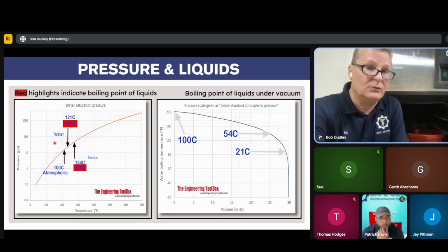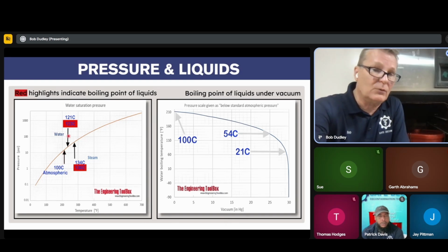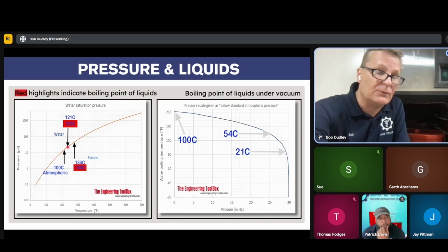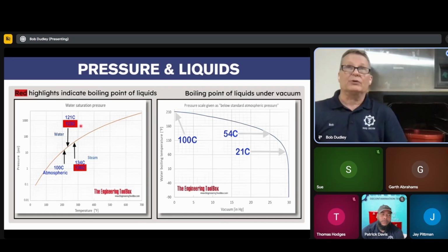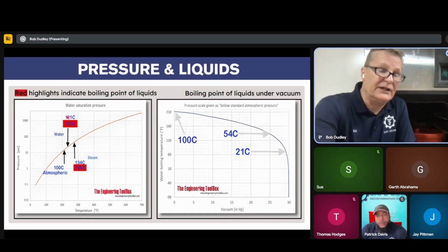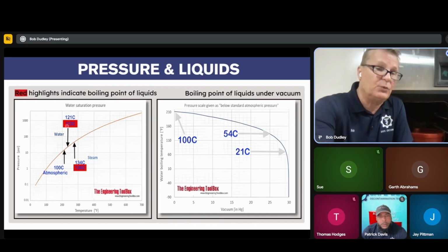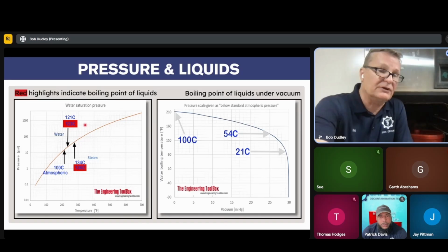And again, that's pressure between water and steam. But for the sake of it, we're going to go with atmospheric being here, 212, 100. Everybody runs this number right here: 15 PSI, which equals 121 Celsius. That's where generally everybody runs this thing. Now, if you have any liquids in your bag, your boiling point becomes, I rounded it up, actually 122.6. So at 122.6, you're not boiling anything. That water is just sitting there.